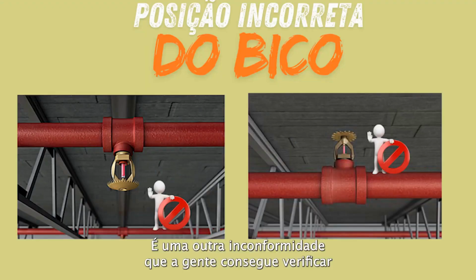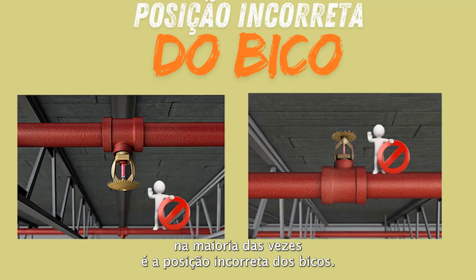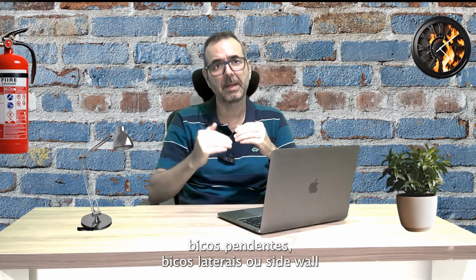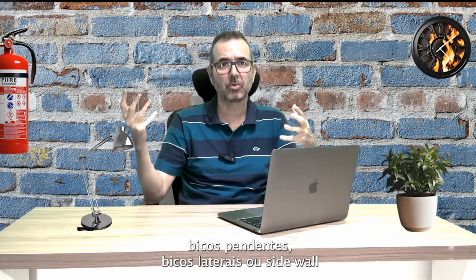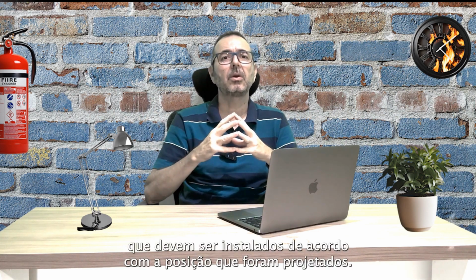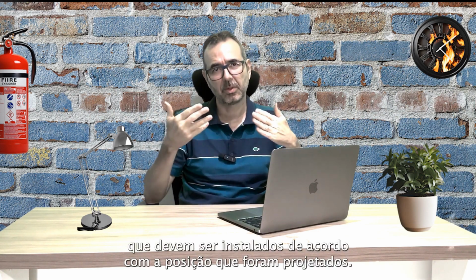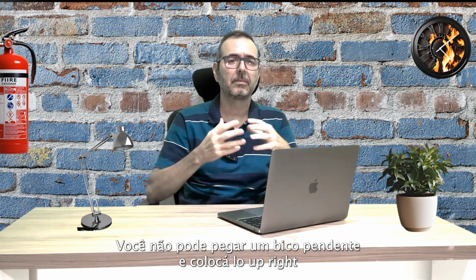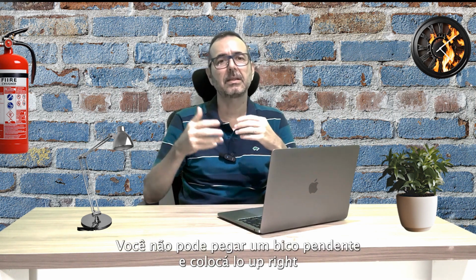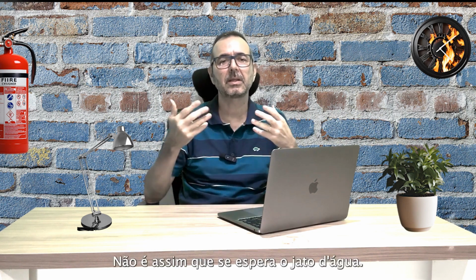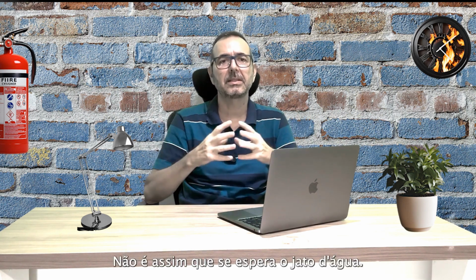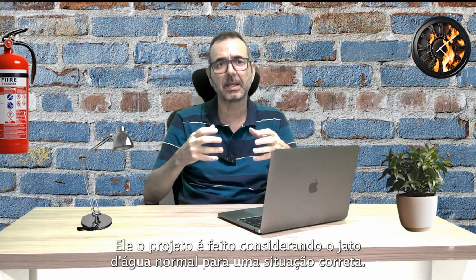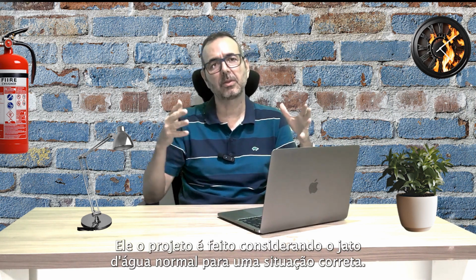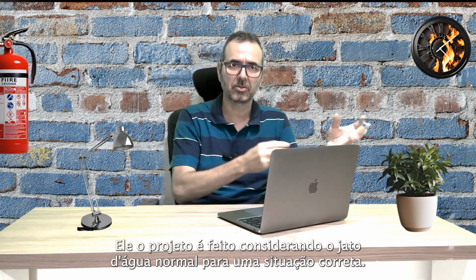Another non-conformity that we often observe is the incorrect positioning of the nozzles. There are upright nozzles, pendant nozzles, and sidewall nozzles, which should be installed according to the position they were designed for. You cannot take a pendant nozzle and place it in upright position. This is not how the water spray is expected. The design is made considering the normal water spray for a proper situation.